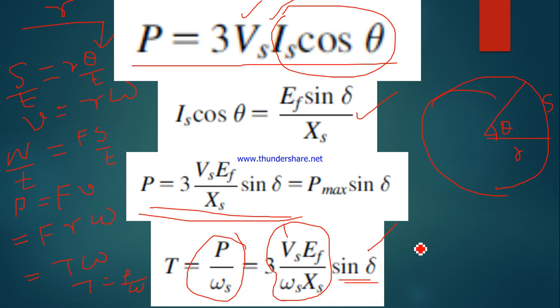The synchronous machine can basically work as a capacitor. You know, a capacitor will push. Capacitor means its reactance is 1 by j omega c, so it will lead. It will move the current phasor nearer to the voltage phasor, which will reduce the loss.